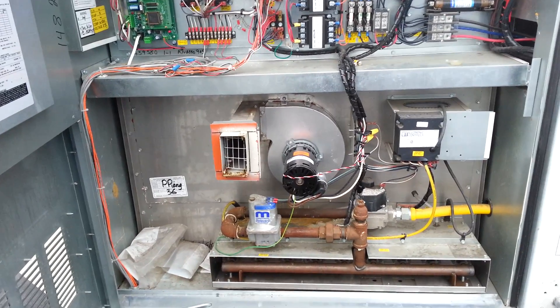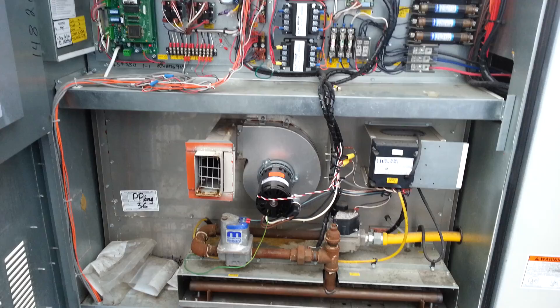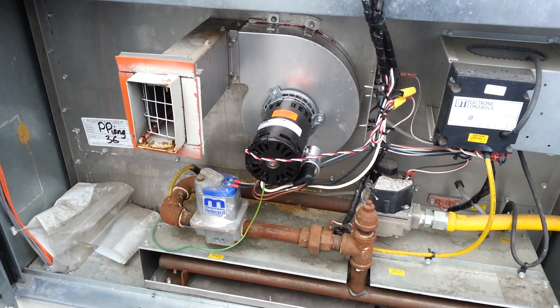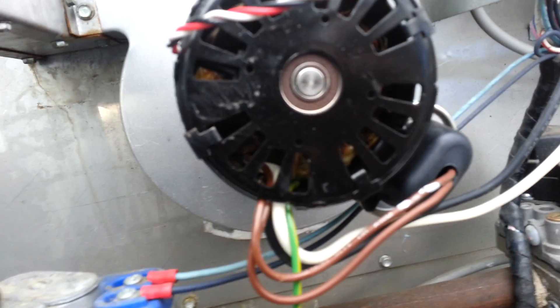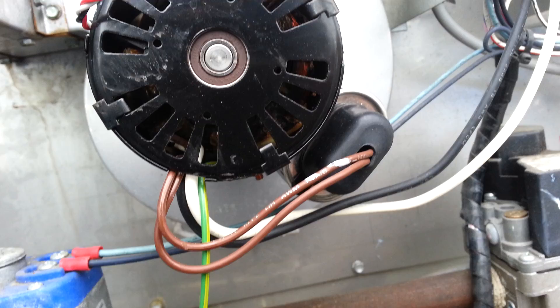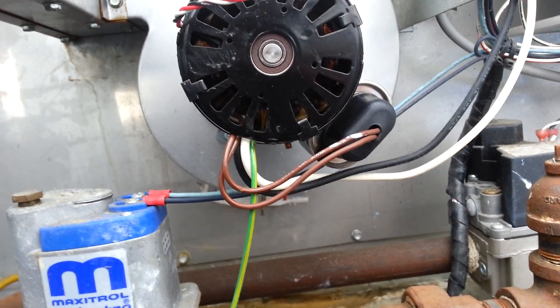I'm working on this Aaon unit. It's had this combustion blower motor replaced about a month ago, and now — the windings are nice and charred, and it's failed open.